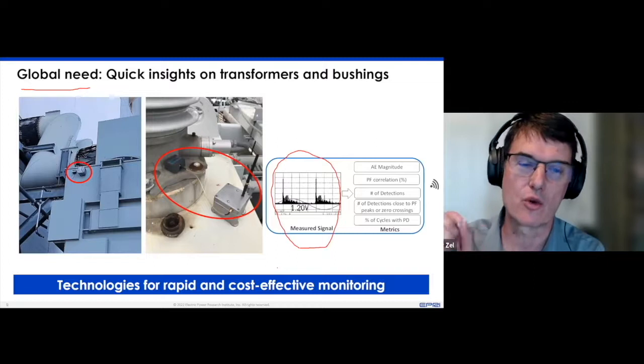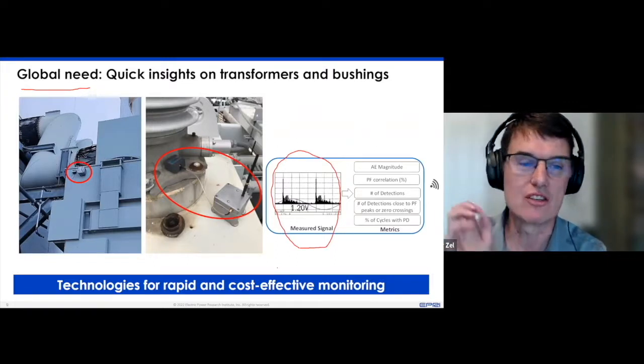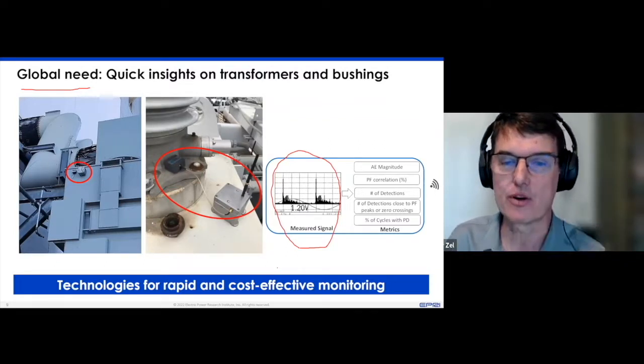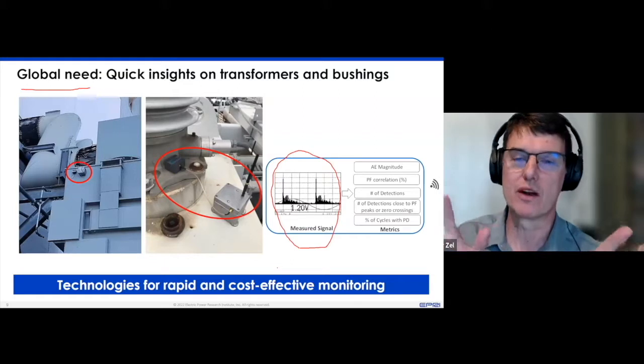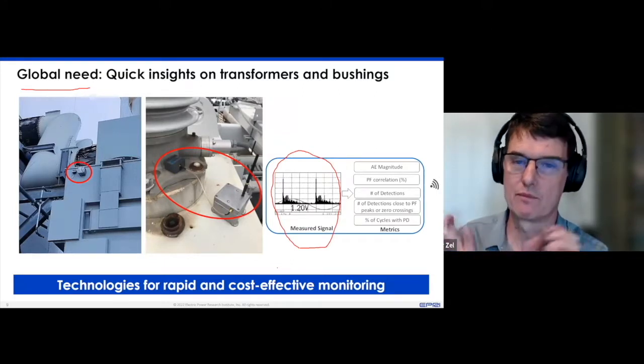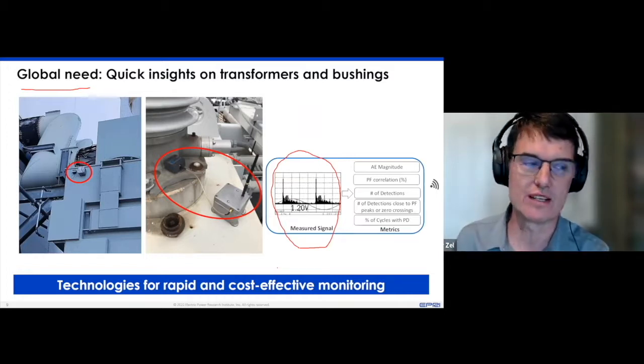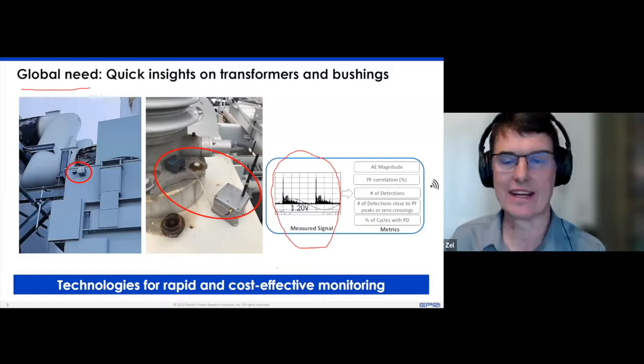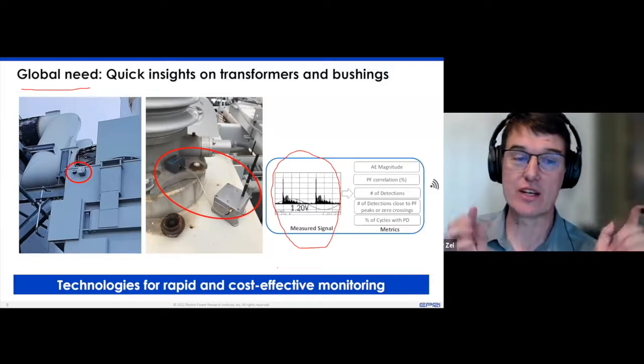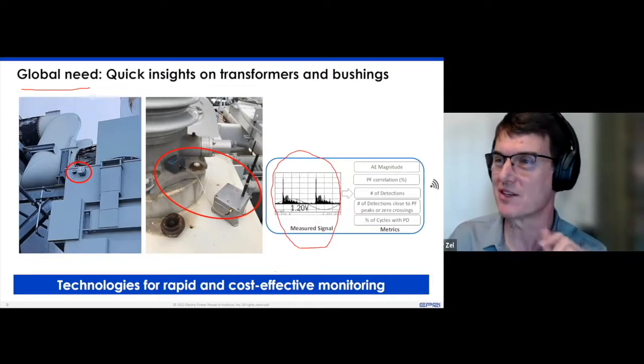You heard Marco talk about the importance of online monitoring of PD. It comes and goes. You need to look at it continuously. So in this approach, we've developed a suite of monitors that can measure, for example, partial discharge, and then send those metrics straight to your desk without an outage and getting it to you really quickly.